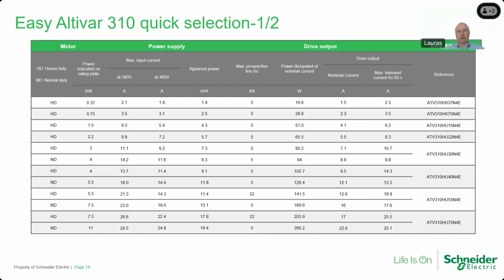And how to properly select the drive. As I said, I will show the catalog later and explain more. But by default, the drive is used for heavy duty application. It means if the drive is, let's say, 3 kilowatts, by default it's heavy duty. It's designed to work with a 3 kilowatt motor, with a nominal current of 7.1 amps, and overload of maybe 150% by current for 60 seconds.